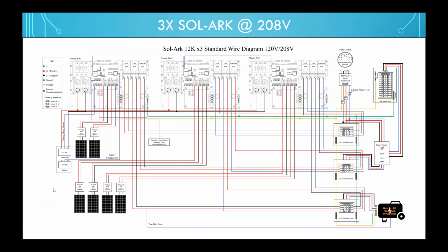So obviously it follows the same lines as the other diagram before. But if you take a hard look inside the user areas as far as the AC, you'll notice that where we are leading with A phase on master phase A, then it has to be leading the next phase, which in this case would be phase B. So it is pretty interesting when it comes down to the wiring. So again, just making sure everything's labeled appropriately.